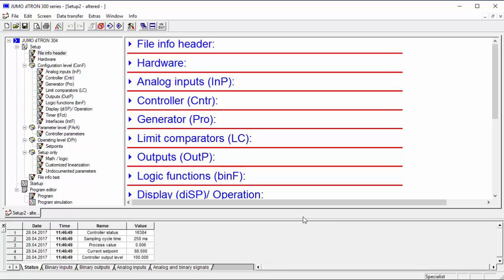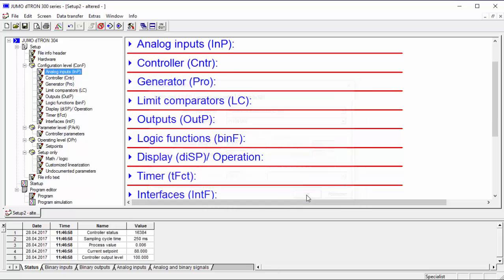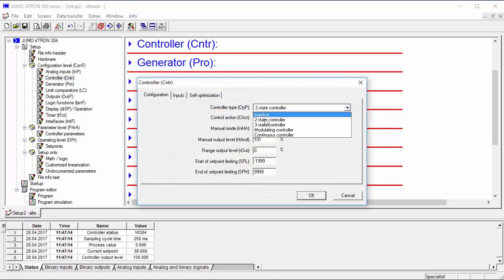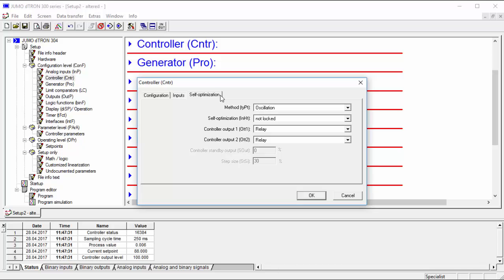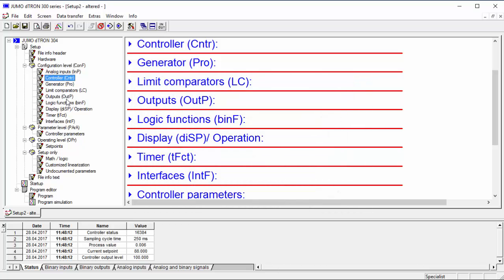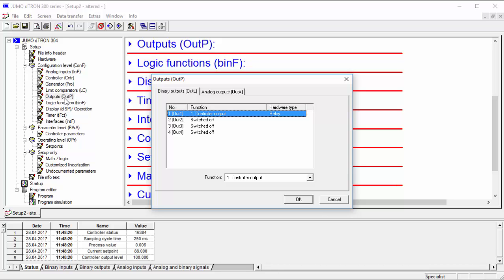With the used RTD temperature probe, the factory setting in the menu Analog Inputs can be utilized. Continuous controller must be chosen in the menu Controller. For auto-tuning, it must be defined that the used controller output 1 for heating exists as an analog output. Some kinds of controllers have 2 outputs regarding the controller function. For example, heating and cooling of the three-state controller is done via the so-called first and second controller output. The continuous controller of our example has only one output regarding the controller function.